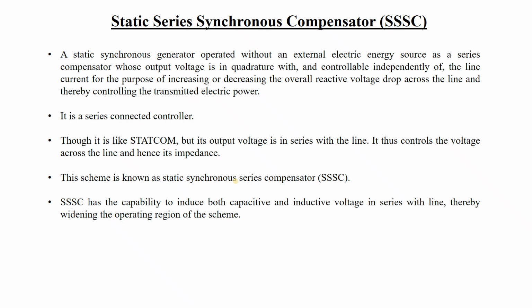The application is the same, the configuration is different. Configuration wise it is series connected, while STATCOM was shunt connected. But here also it is doing the same thing: it supplies the voltage in series with the line, whereas in STATCOM we have seen that it controls the voltage in shunt, parallel to the line. Since SSSC controls the voltage in series with the line, it also controls the line impedance. The major purpose remains the same: it is used as a reactive power compensator. It can induce both capacitive and inductive voltage, but this time in series with the transmission line.